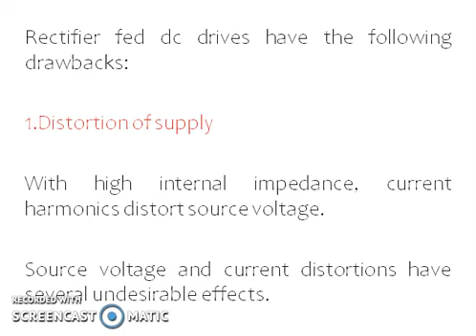The rectifier fed DC drives has a few drawbacks. The first one is distortion of the supply. As the source current of the rectifier has harmonics, in a weak AC source with high internal impedance, current harmonics distort the source voltage. Therefore, the temporary short circuit of lines during the commutation of thyristor causes sharp current pulses, and these pulses again distort the source voltage. The source voltage and current distortions have several undesirable effects, including interference with other loads connected to the same source and radio frequency interference in communication equipment.